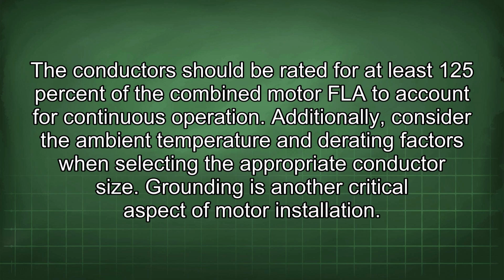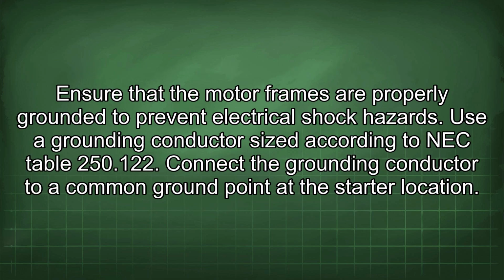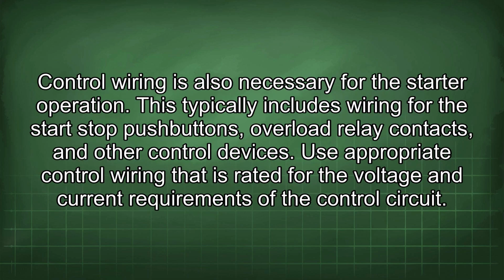Grounding is another critical aspect of motor installation. Ensure that the motor frames are properly grounded to prevent electrical shock hazards. Use a grounding conductor sized according to NEC Table 250.122. Connect the grounding conductor to a common ground point at the starter location. Control wiring is also necessary for the starter operation. This typically includes wiring for the start-stop push buttons, overload relay contacts, and other control devices.